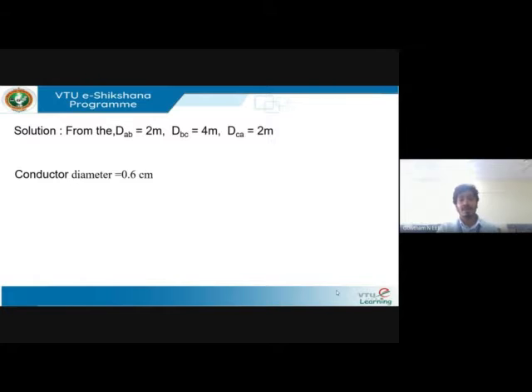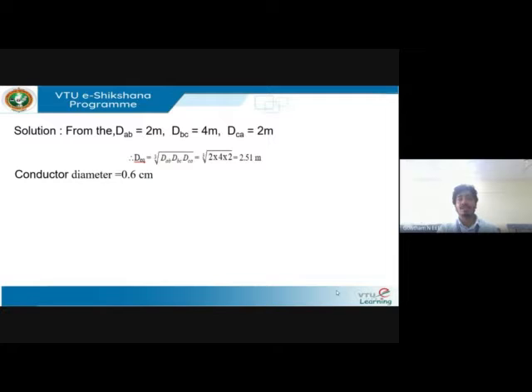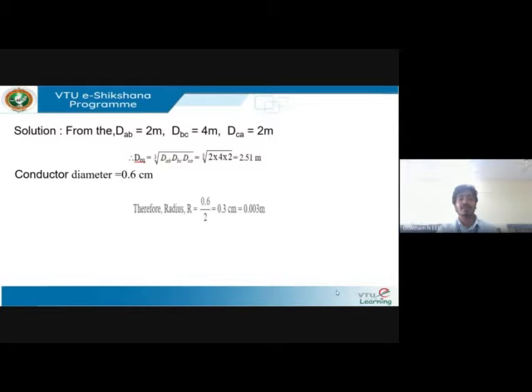From the diagram, the given value of D_AB is two meters, D_BC is four meters, and D_CA is two meters. The formula to find D_equivalent is the cube root of D_AB, D_BC, and D_CA. Taking the cube root of these values gives 2.51 meters. The conductor diameter is given as 0.6 centimeters, so the radius of each conductor is 0.003 meters.